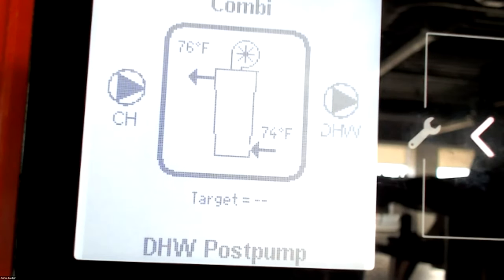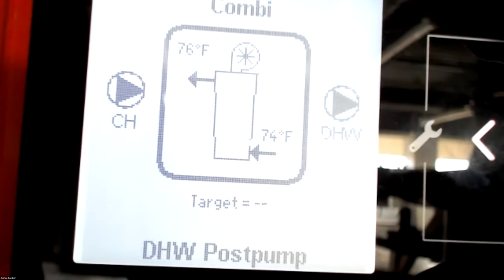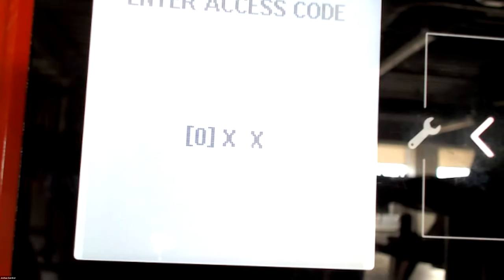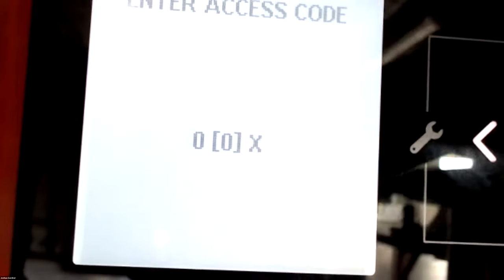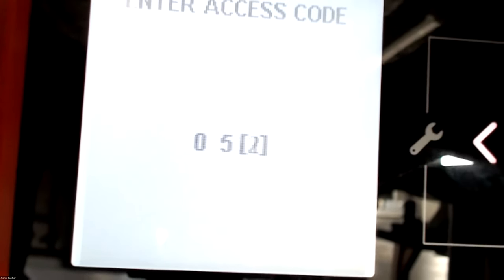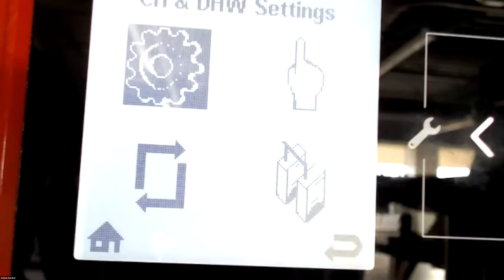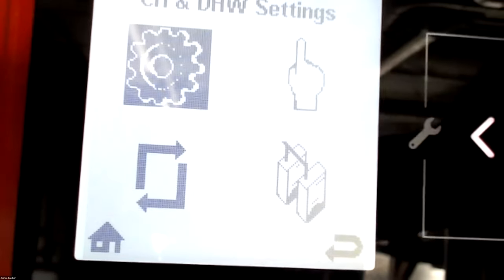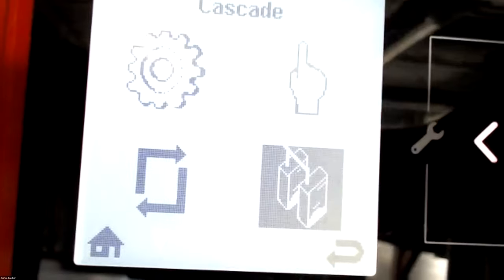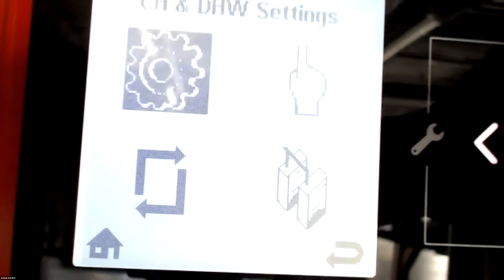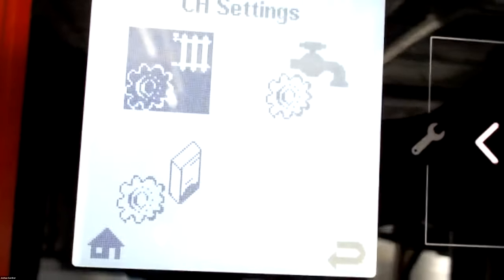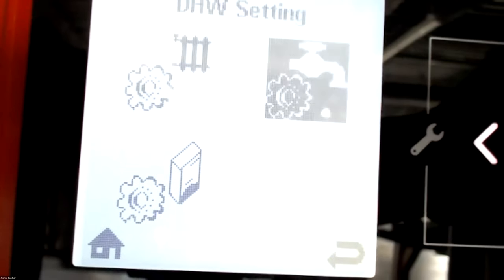Now we're going to go into the installer settings. And all we're going to do is hold the up and down arrows for about 5 seconds. And it's going to ask us for the installer access code. This access code on all of our boilers is 054. Not in our manuals, but note it, 054. So from here, we have our CH/DHW settings, reset all settings, cascading settings, and manual operation. So if we start in with our CH/DHW settings: boiler settings, CH settings, and domestic settings.